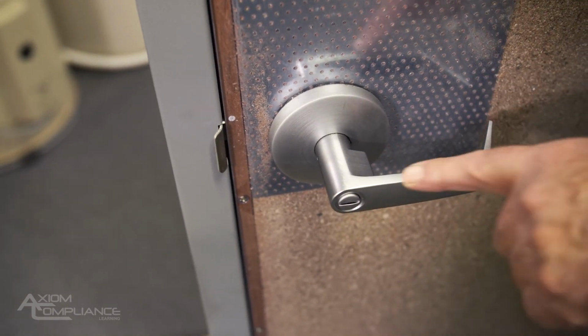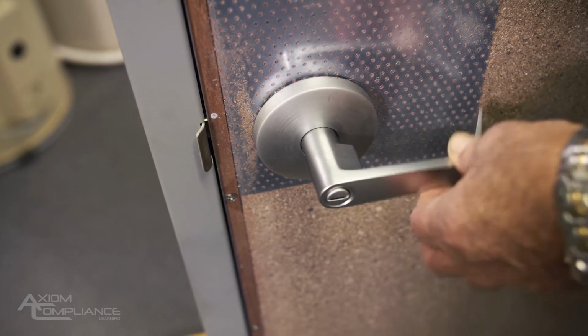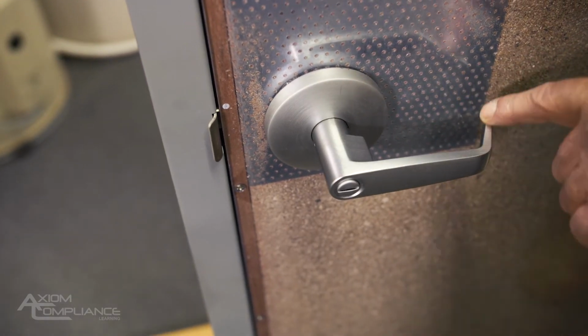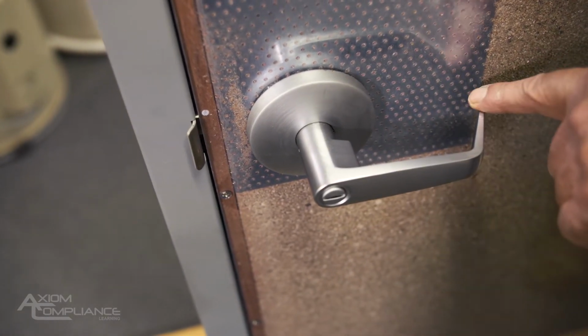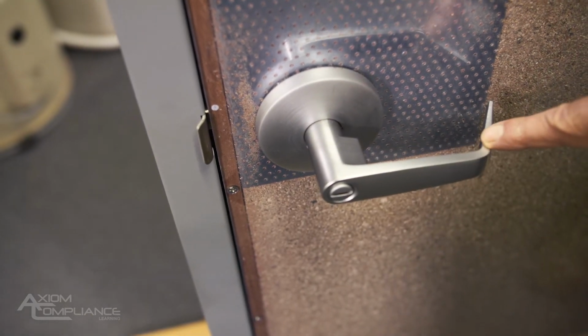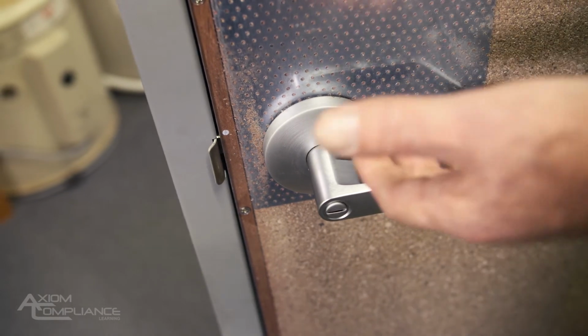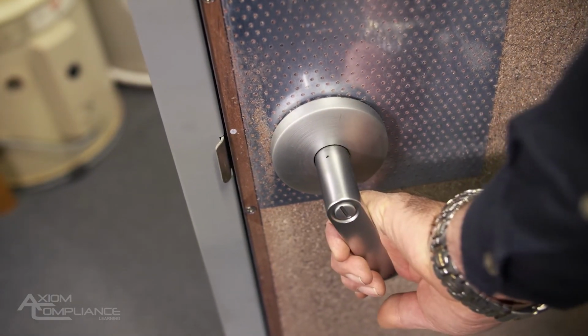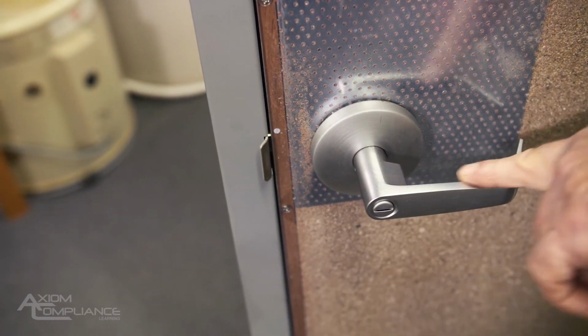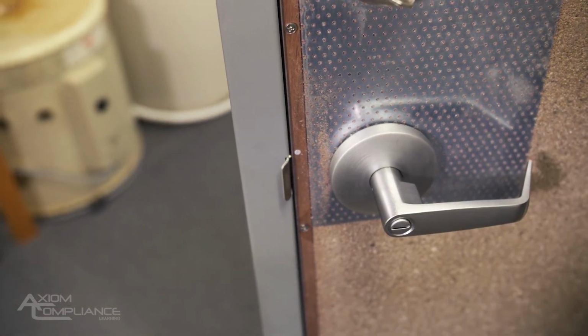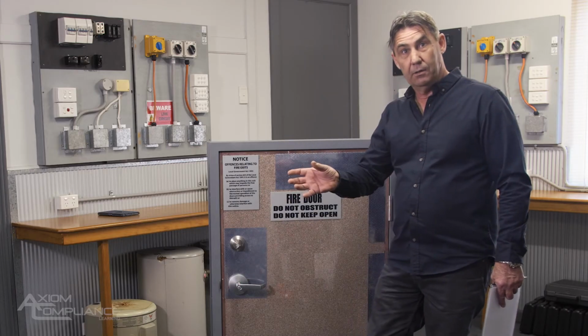In general, and it's not an absolute requirement, just a lever action is all that's required, but the D-shaped handle is generally the handle that the manufacturer will make when it's fire rated so that your hand doesn't slip off it. So the standard says you've got to have a lever that the hand doesn't slip off, and that's what the manufacturers do to stop that. They use a D-shaped handle. So it can't be a knob.